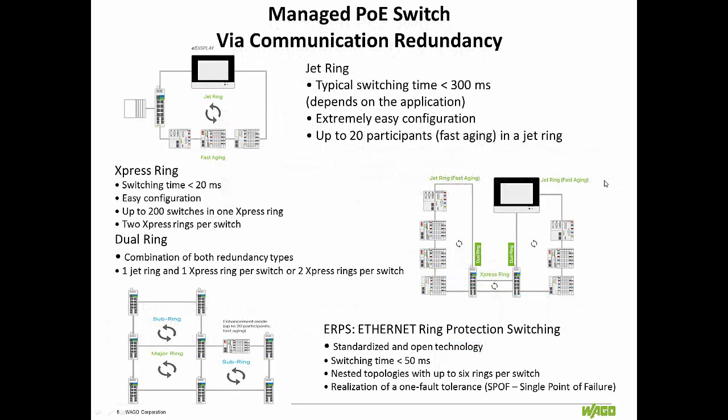Network redundancy is an important consideration for many industries and applications. With the WAGO switches, there are many redundant network options, such as jet ring with switching times of less than 300 milliseconds. Also, express ring setup, dual ring, and Ethernet ring protection switching is available.